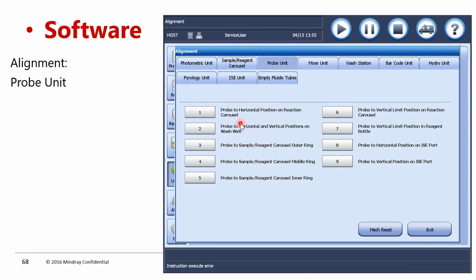Different positions: how many positions does the sample probe have? The probe goes to the wash well position, right? Then the reagent sample position, meaning the outer position of the outer disk, the reagent disk outer position, that is the sample position. Then the inner ring and middle ring, four positions, and the cuvette. This sample probe will go to all these places, so you have to verify alignment in all of them. At every position you have to make it horizontally centered, and also verify vertically how deep it is going, and adjust accordingly.